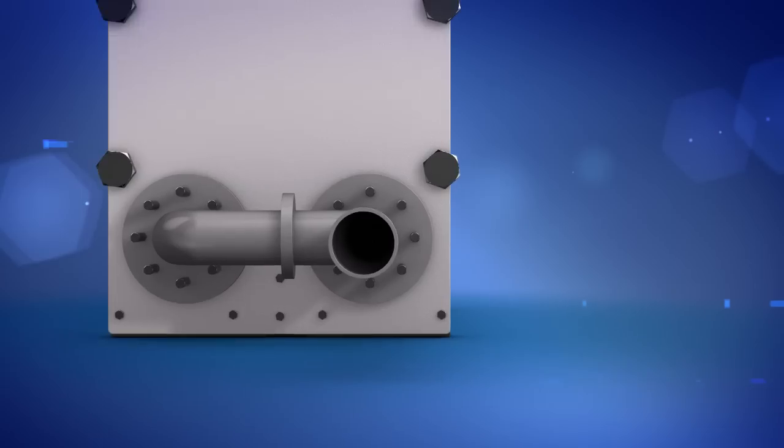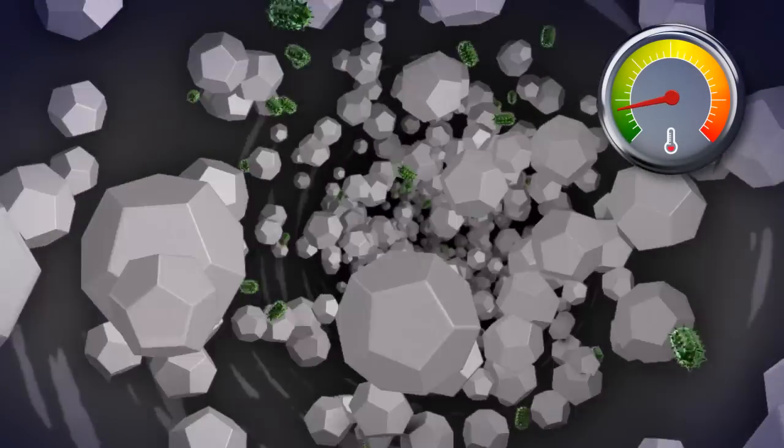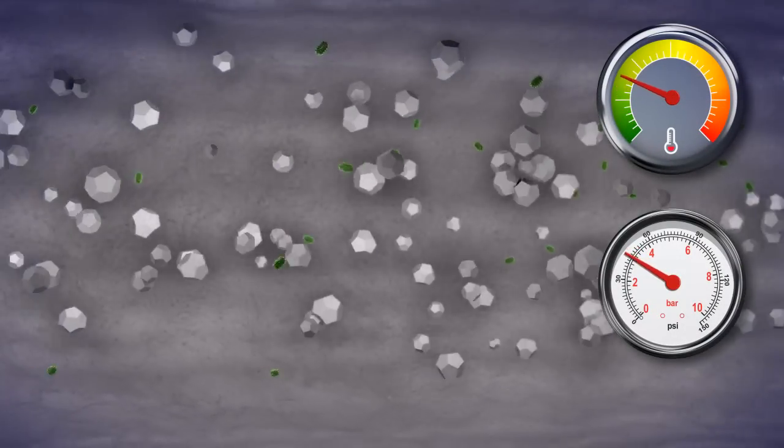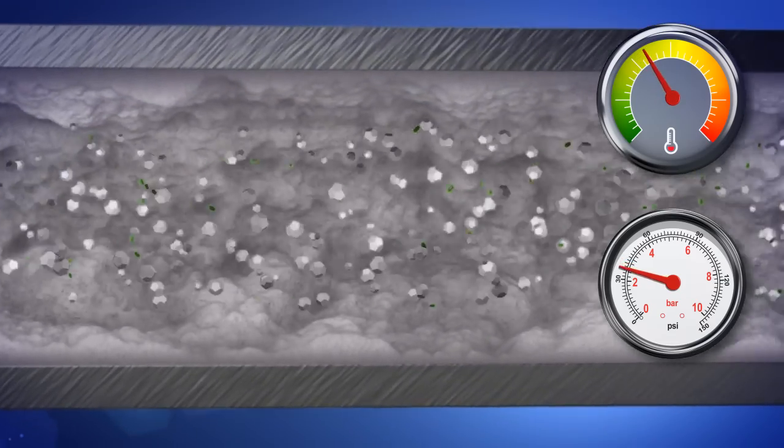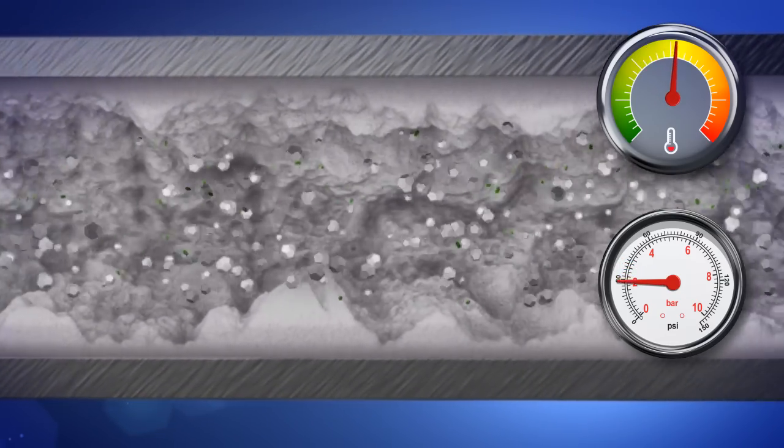A liquified solution inside a pipe system may contain minerals such as calcium carbonate dissolved in the forms of ions. When temperature increases or pressure drops, the solution becomes supersaturated, which causes the ions to adhere to piping and equipment surfaces in the form of scale.